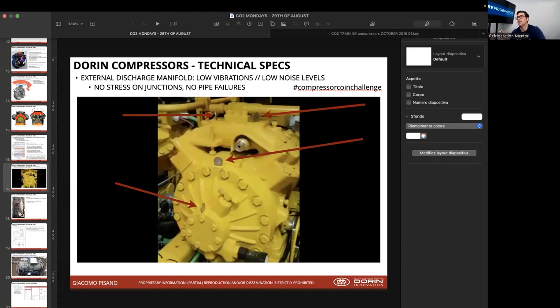To illustrate, we have a hashtag 'compressor coin challenge' on LinkedIn where you'll find examples of our compressor running with coins standing vertically on it. It doesn't make practical sense to put coins on a compressor, but it gives you an idea of the smooth running and you'll hear a very smooth sound. The technical explanation is, again, the external discharge manifold. So the plenum gives you multiple benefits: lower oil temperature, no minimum discharge temperature requirement for lubrication, and less noise and pulsation — which is very important because I've seen discharge lines and suction lines break due to vibration.